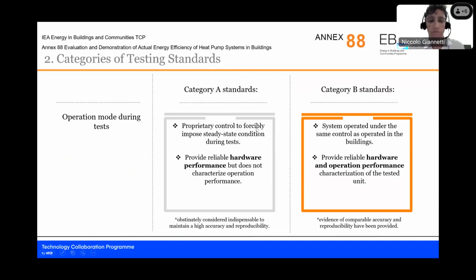So just to be clear, again, this slide clearly states what the differences are between category A and category B standards. Category A standards, or current standards, are required tests that are conducted by utilizing some special kind of test control, so proprietary control, that forces the system into a steady state operation during test that would not necessarily occur in the actual operation.